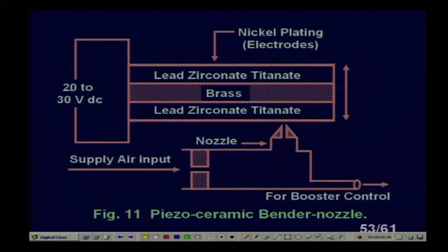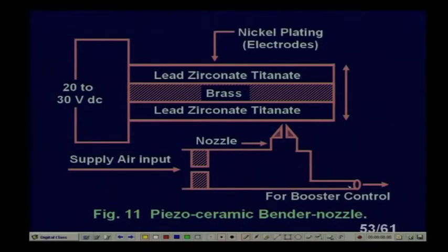This pilot pressure will be a function of the DC voltage we apply to the flapper nozzle at this ceramic. And this voltage, again, is a function of the current which is coming in. So whatever pilot or back pressure I am getting here is proportional to, a function of, exactly the current which you are getting.